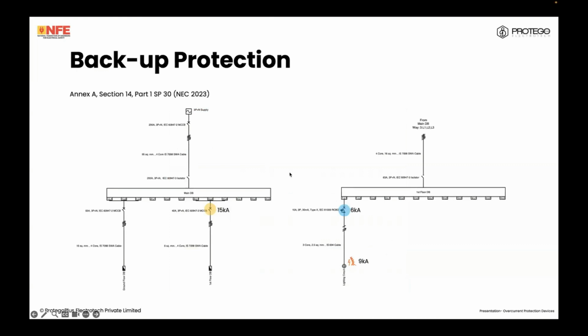Backup protection is a little interesting. So say I've got this, this is my distribution circuit, this is my main circuit, and from the distribution circuit, this is the final load, this is the lighting circuit. Say I have 9 kiloamperes of fault here, but Icu or Icn for this circuit breaker is only 6 kiloamperes. Now, this can obviously not clear this fault without damage, but this is rated 15 kiloamperes. What may happen is that this 9 kiloamperes fault may only be seen for faults that are happening very near the circuit breaker. For faults away, this is not really an issue. And say this is an armored cable or that, the possibility of faults is much lower here.